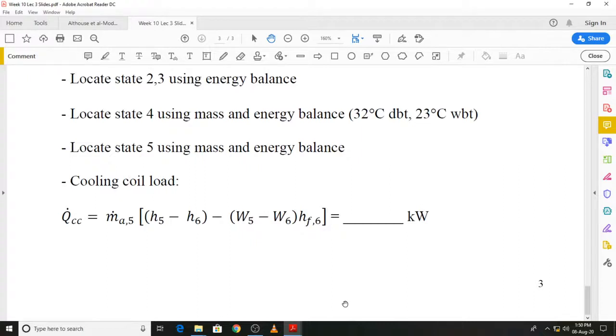If you refer to the psychrometric diagram, you can see that we now have three states which are yet to be located, that is state 2, state 4 and state 5, and they can also be found out by applying energy and mass balances. Because state 2 or state 3 is obtained by the mixing of the two states, that is state 2a and 2b, we can perform an energy balance, and that will give us state 2. State 4 is the condition of the outside air, and that is given to us, so we can easily locate state 4.